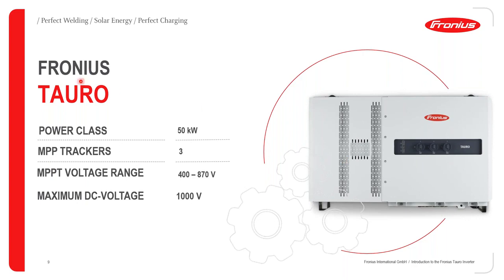But anyways, with the Tauro, you have 3 trackers. Okay, so this is really good for field installations that are all pointing in different directions. And MPPT voltage range is quite wide, from 400 to 870 volts DC, and your maximum DC voltage will be 1000 volts DC per string. Okay, in terms of the weight will be 74 kilograms.